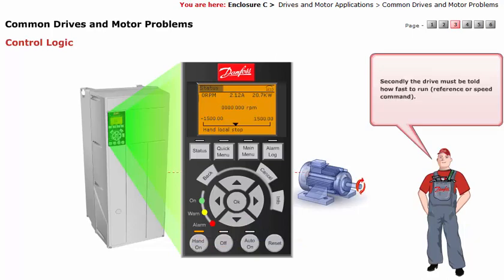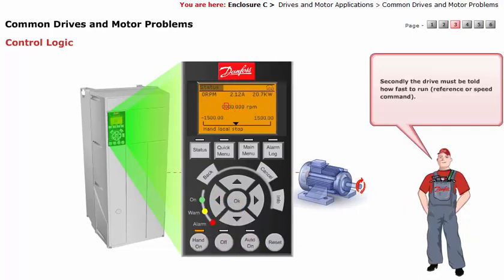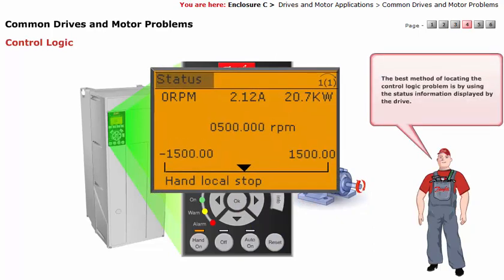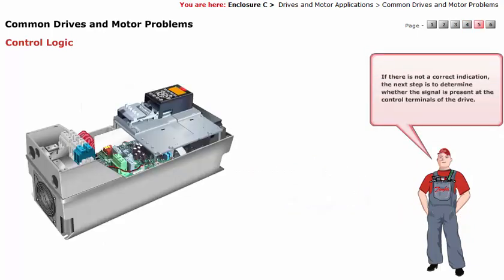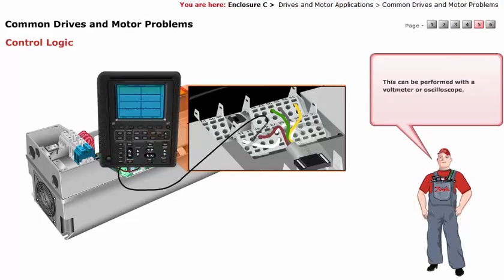Control logic problems occur when the drive does not respond to a given command. There are two basic commands that must be given to any drive in order to obtain an output: first, the drive must be told to run; secondly, the drive must be told how fast to run. The drives are designed to accept a variety of signals. The best method of locating the control logic problem is by using the status information displayed by the drive.